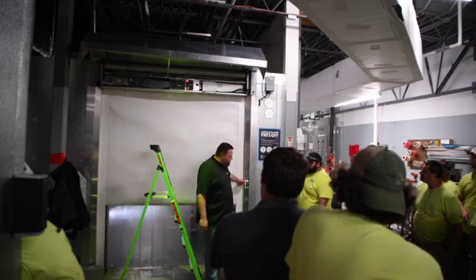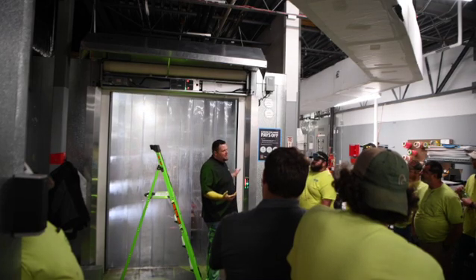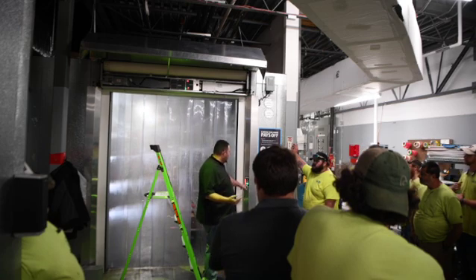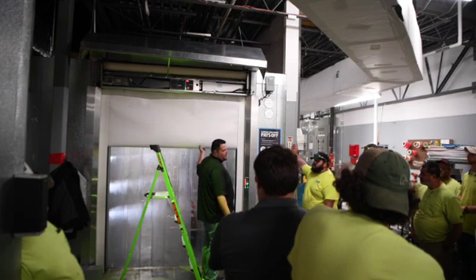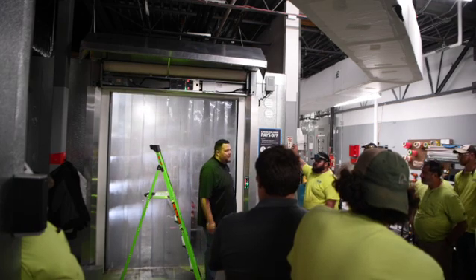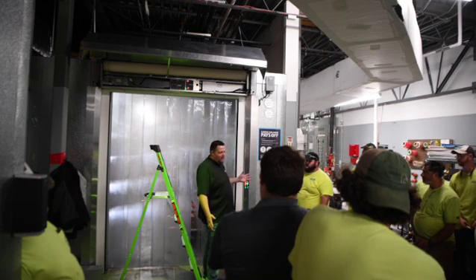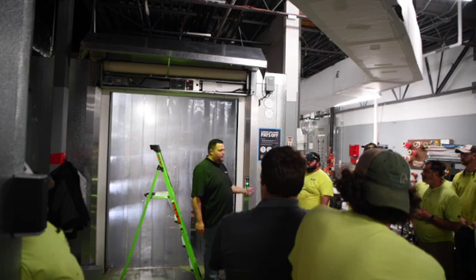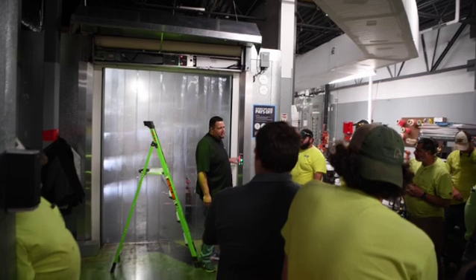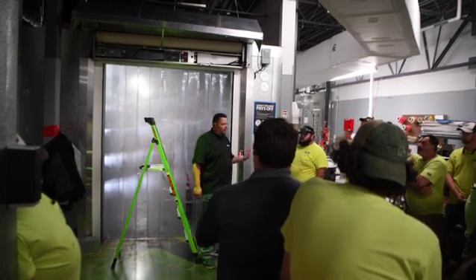So then the third option, you have lead edge. The lead edge is a light that's going to flash when the door auto reverses. That's if this door tries to come down and it catches something like a panel or a buggy that's not interfering with the lights, it's going to auto reverse. But all you're going to see is an immediate flash, and then it's going to go to everything flashing again. So it's one of those quick triggers that you watch. That's the same thing for either auxiliary safety or lead edge. It doesn't stay lit by itself. It's only going to light up the moment there's an issue.